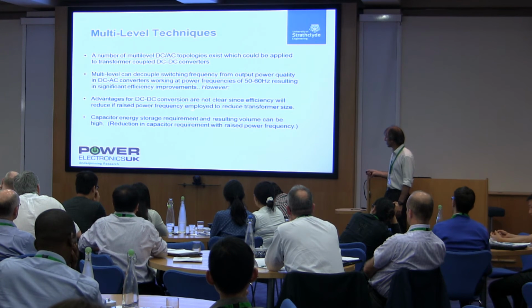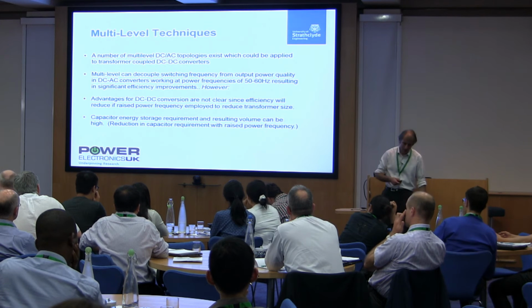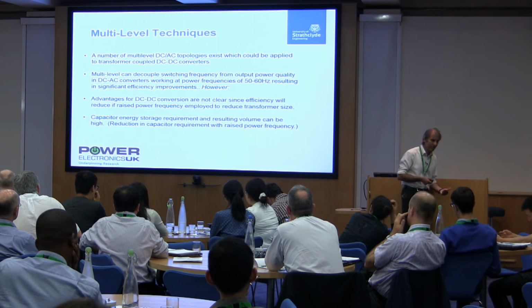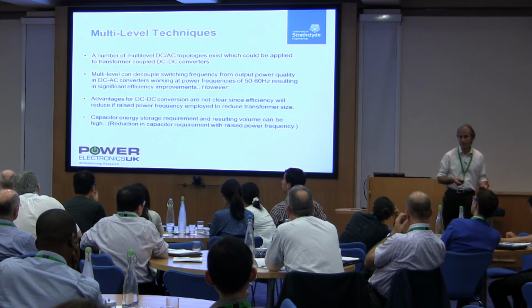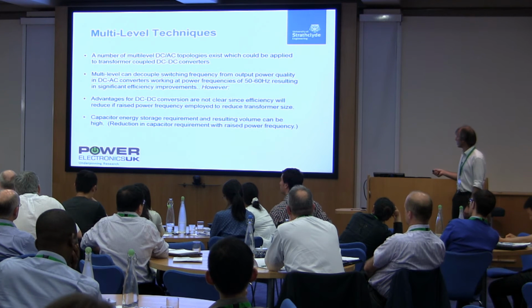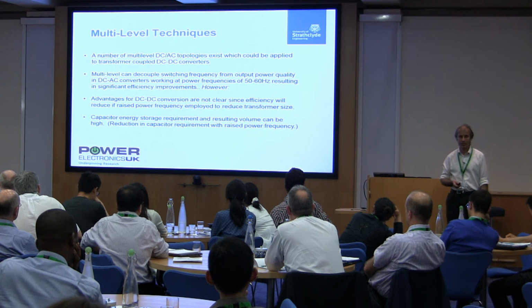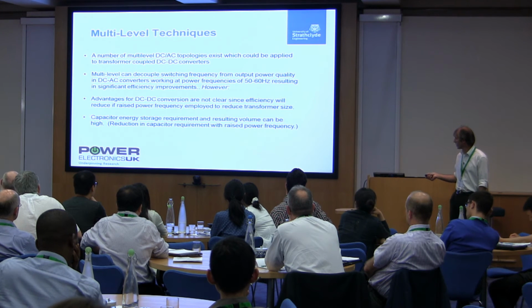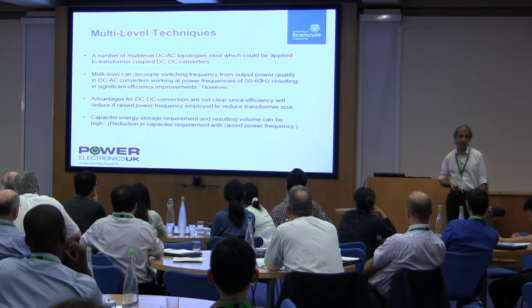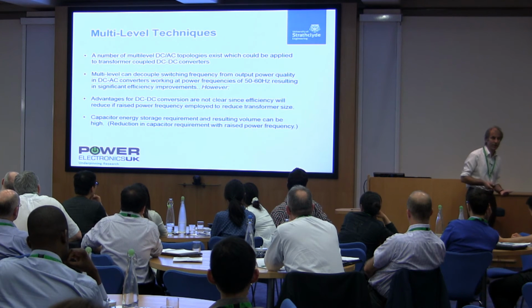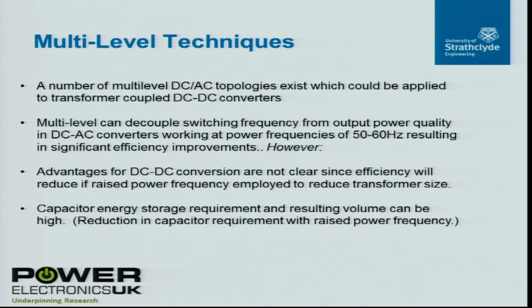We can raise the power frequency, and if we talk about medium frequency, maybe up to 400 hertz, you certainly could just translate an MMC type topology to that. Indeed, there'd be some advantages because one of the problems with the MMC converter is the size of those capacitors. You saw the diagrams in the last presentation. They're a big part of the converter.